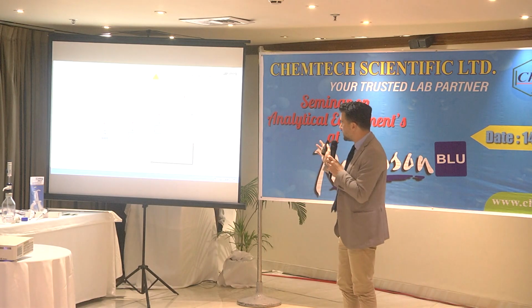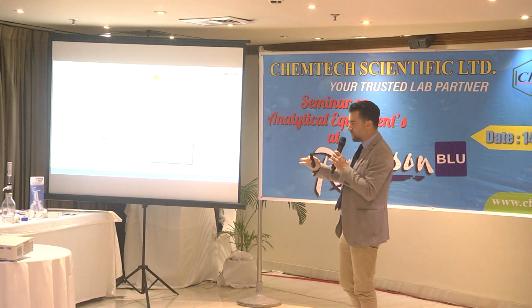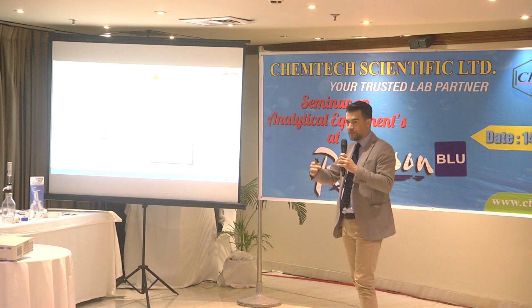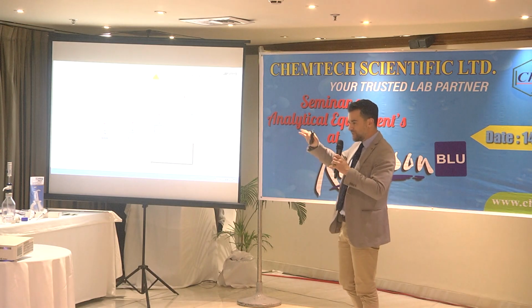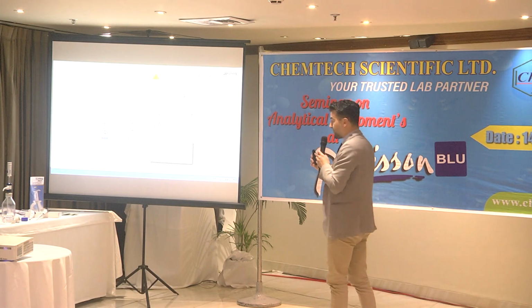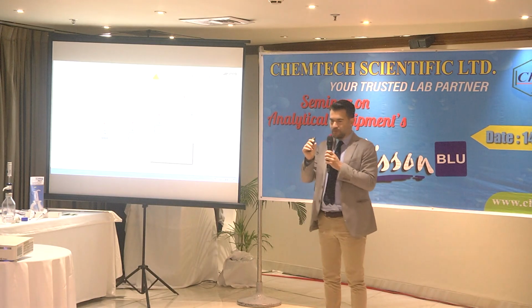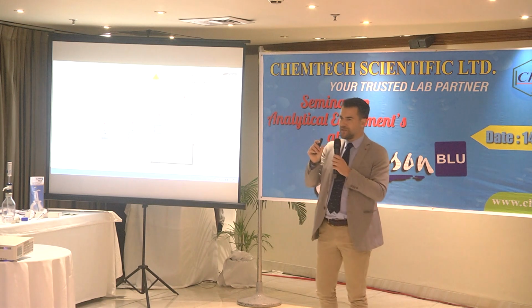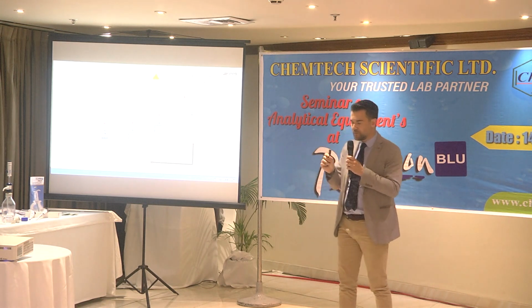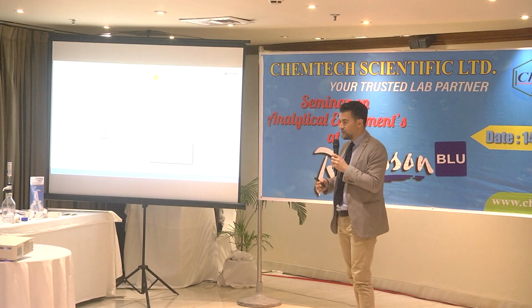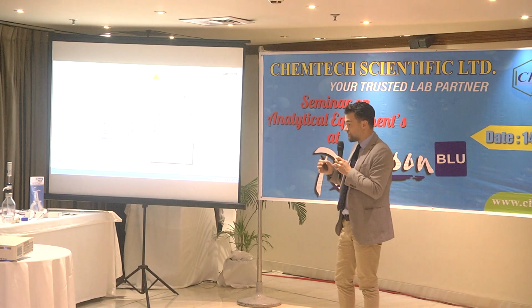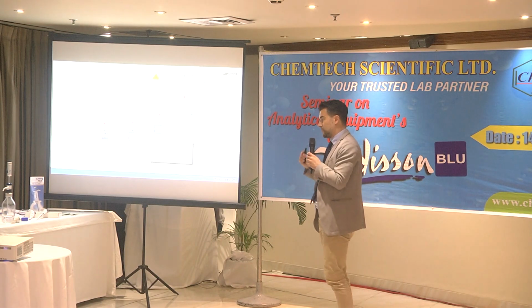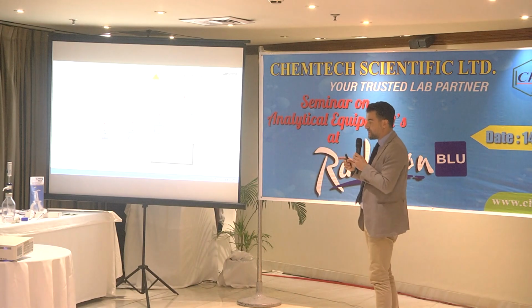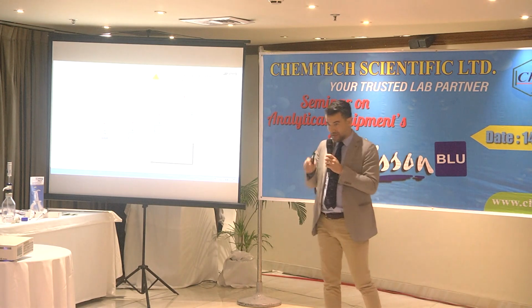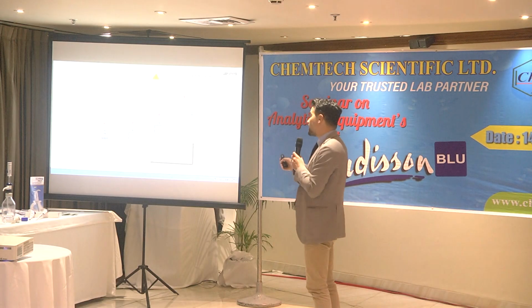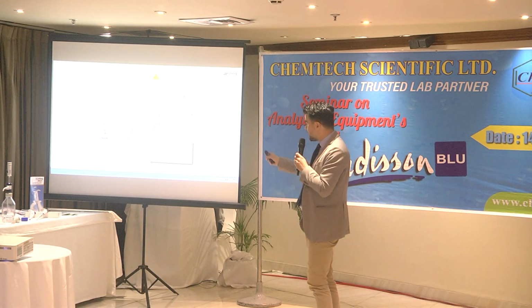a high dimension chamber, and on one level you can wash bigger reactors or big bottles, 10 liters or more, because you don't have any limitation in space. Or if you want to wash, for example, small vials, test tubes or small volumetric flasks, 25 milliliters or 50 milliliters, we have a trolley accessory that can accommodate up to 208 pieces each level. If you consider 3 levels, there are more than 600 pieces every cycle that you can wash at the same time. So this is a really high capacity machine, the 6290.